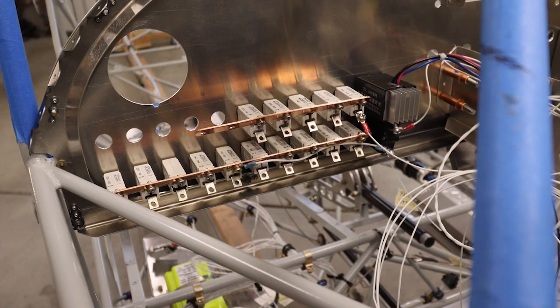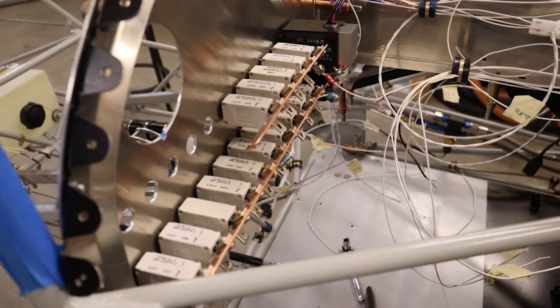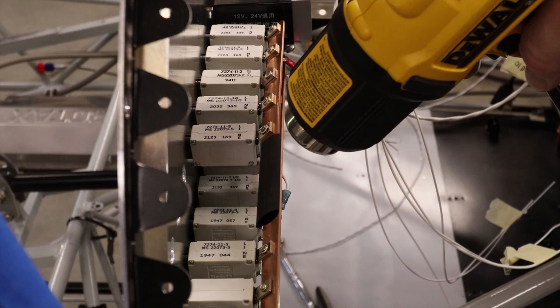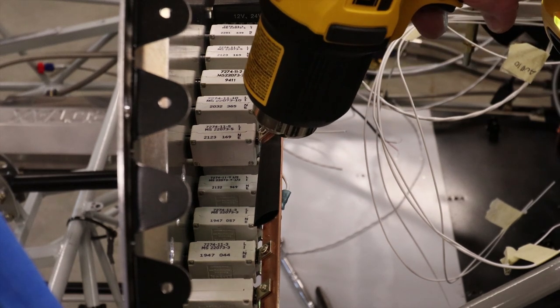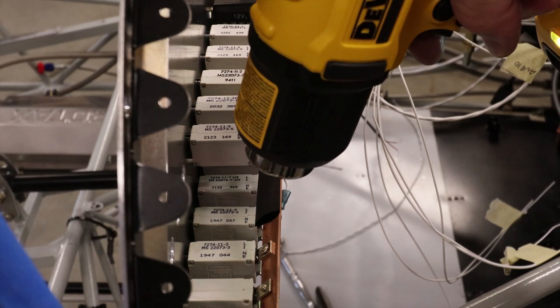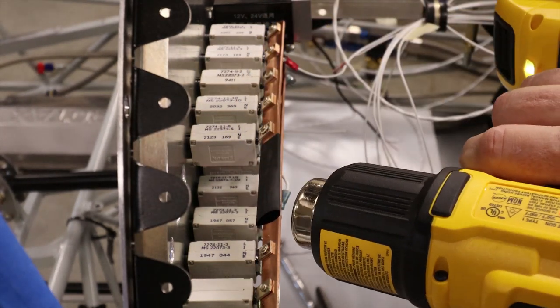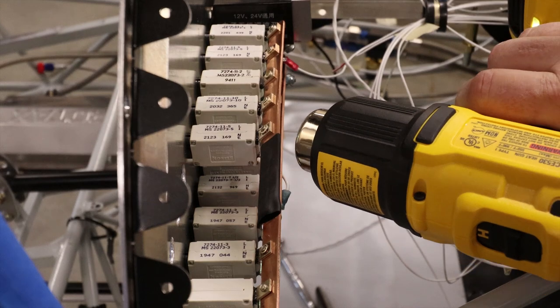Since the circuit breaker is a termination point of a harness, the right side panel became a collection point. Mounting the circuit breakers and bus bars first, I was able to neatly terminate a wire to its exact length. As I mentioned in my previous video, for future expansion I drilled extra holes for additional circuit breakers, so I left the bus bar a little long, covering it with shrink tubing until I needed it. Always leaving room for expansion - you'll thank yourself someday in the future.